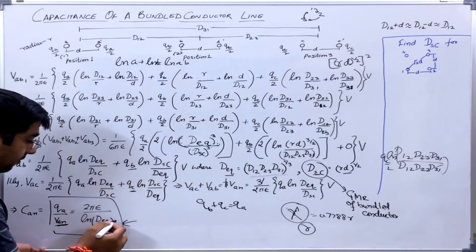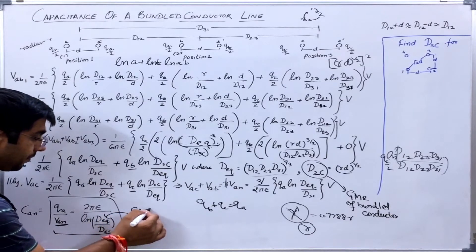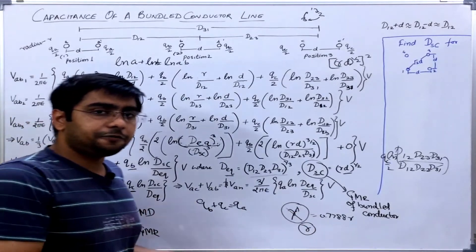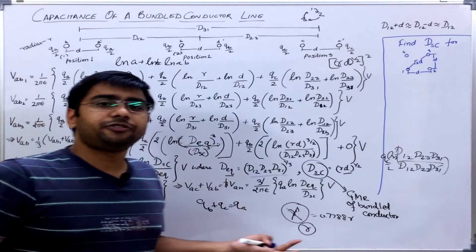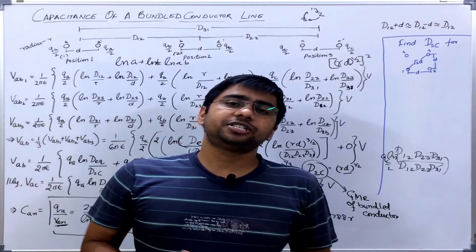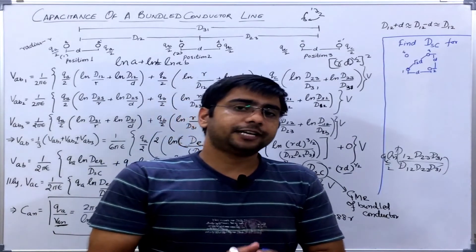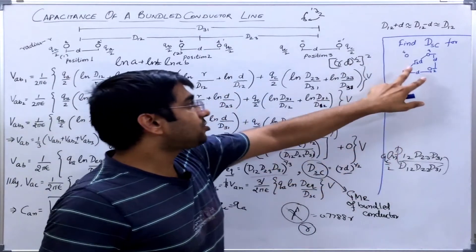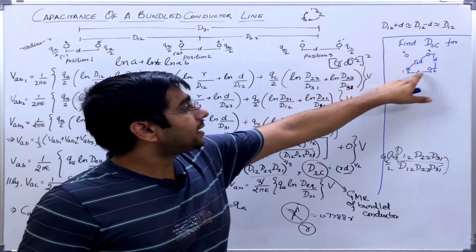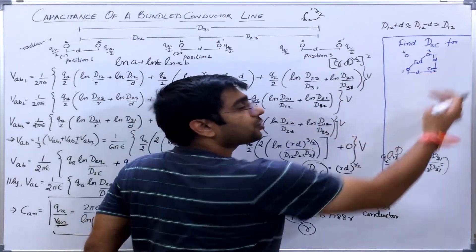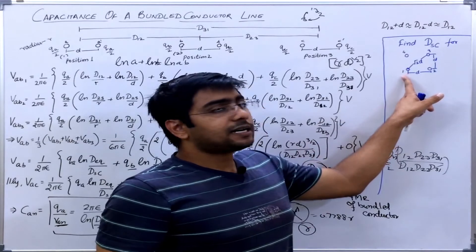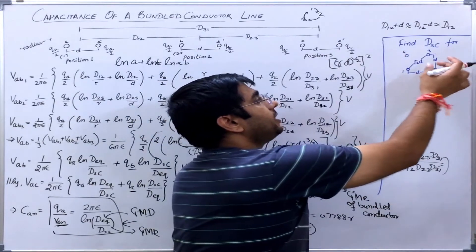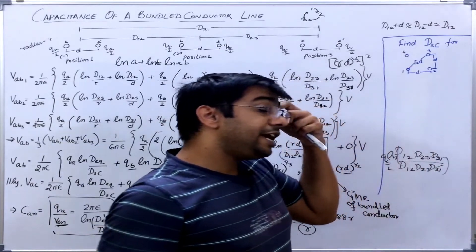This is a very simple formula — D_eq plays the role of GMD and D_sc plays the role of GMR. So it is easy to calculate the capacitance of any kind of configuration if we know how to calculate the GMD or GMR. For an example, let us derive the GMR of a configuration in which bundle conductors have 4 conductors per phase at the corners of a square of side d.